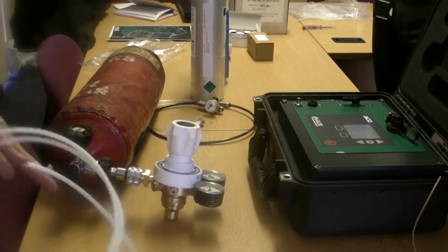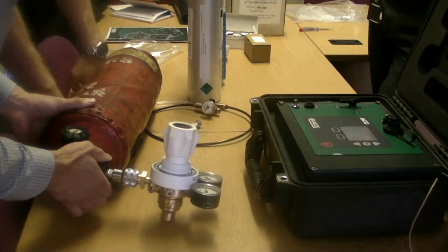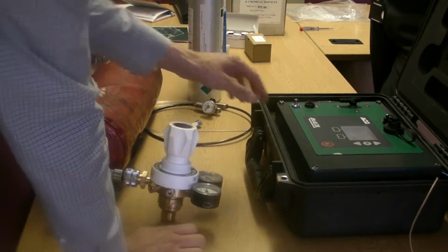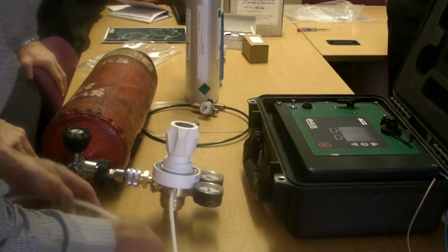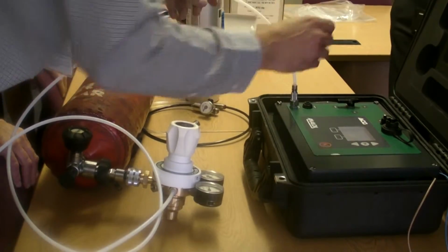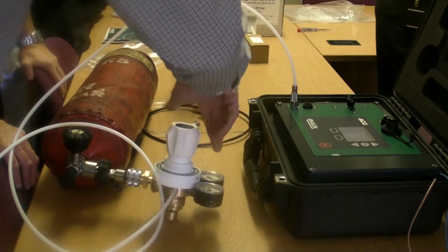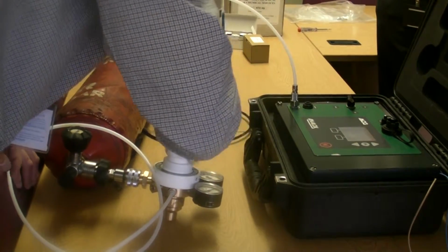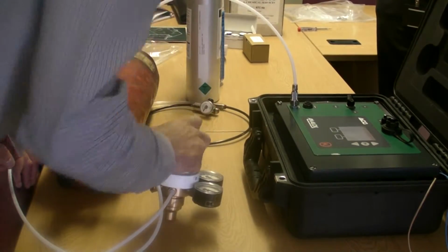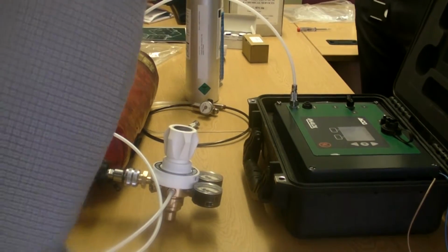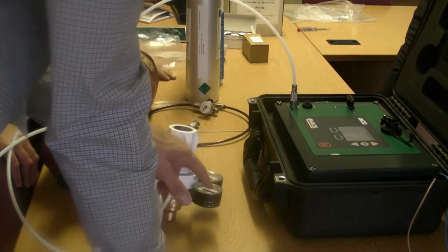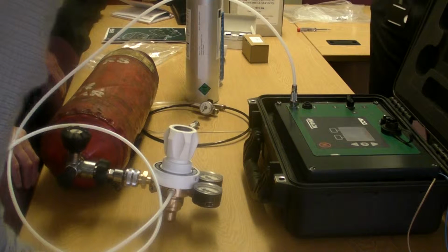We recommend that you calibrate the ACG Plus upon installation and then every 3 months with a low or zero gas calibration mix first, followed by a high or span gas calibration mix. To perform a calibration adjustment, first expose the sensors to the appropriate calibration gas of known concentration via the sample or calibration gas inlet. Fit the 0.5 LPM gas flow regulator accessory or suitable regulator to the calibration gas bottle. Connect the outlet of the regulator to the inlet calibration gas connector accessory and then connect the inlet calibration gas connector to the calibration inlet onto the ACG Plus. Push the fitting on fully until it latches into place. Open the valve on the flow regulator attached to the bottle and then open the inlet valve on the front panel. The ACG Plus should register that there is a flow to the sensors.